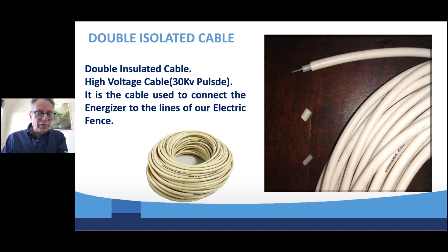Also, you have a first insulation, which is silicone, and a PVC jacket. It also has a chemical process for UV protection. This can handle a 30 kV pulse so you can move the high voltage of the equipment, because the equipment works at 12,500 volts at most. Maybe when you have induction on the same fence you'll have 16K, but the cable is perfectly functional.